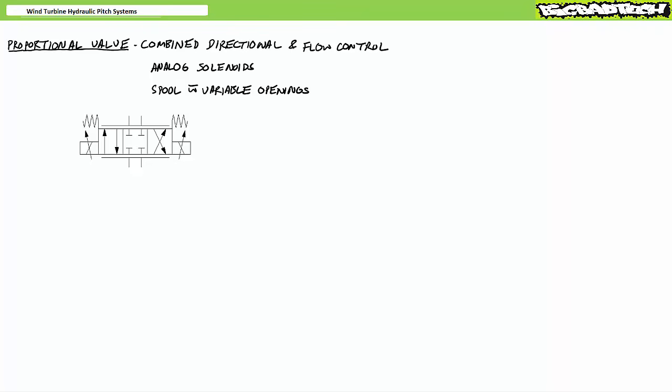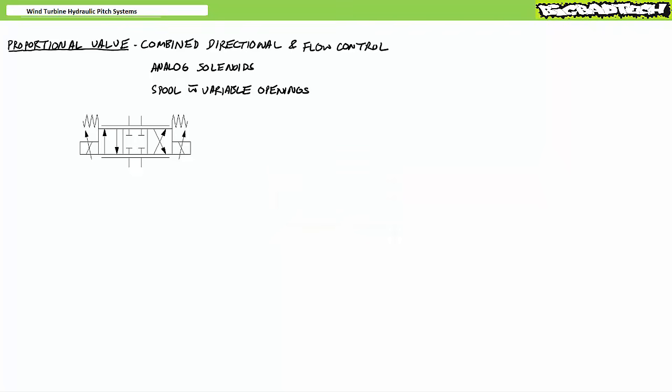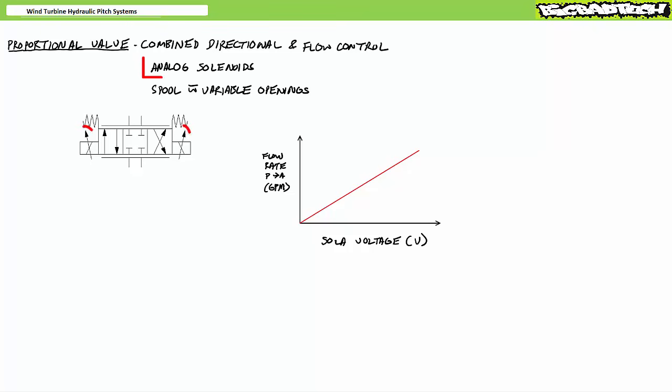I am, of course, referring to analog control afforded by proportional valves. You recall we examined proportional valves extensively in the proportional valves lecture, available at the Big Bad Tech channel. A proportional valve is essentially a directional control valve that, in addition to stopping, starting, and changing the direction of fluid flow, also simultaneously offers the ability to control the rate of fluid flow through them. Two features differentiate proportional valves from regular directional control valves.